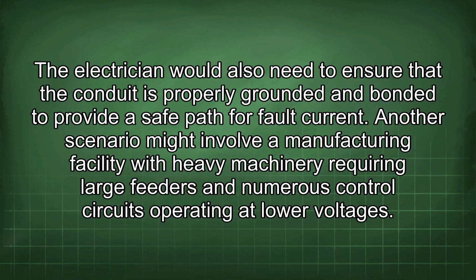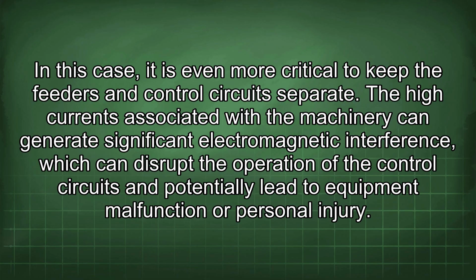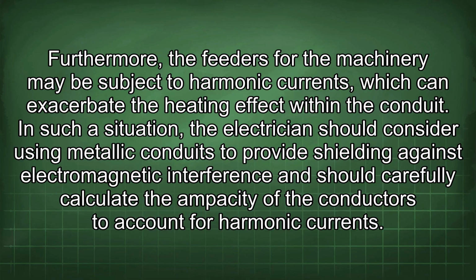operating at lower voltages. In this case, it is even more critical to keep the feeders and control circuits separate. The high currents associated with the machinery can generate significant electromagnetic interference, which can disrupt the operation of the control circuits and potentially lead to equipment malfunction or personal injury. Furthermore, the feeders for the machinery may be subject to harmonic currents, which can exacerbate the heating effect within the conduit. In such a situation, the electrician should consider using metallic conduits to provide shielding against electromagnetic interference and should carefully calculate the ampacity of the conductors to account for harmonic currents.